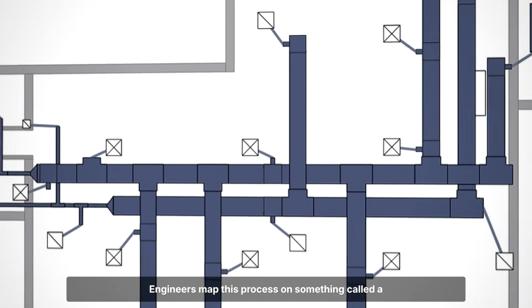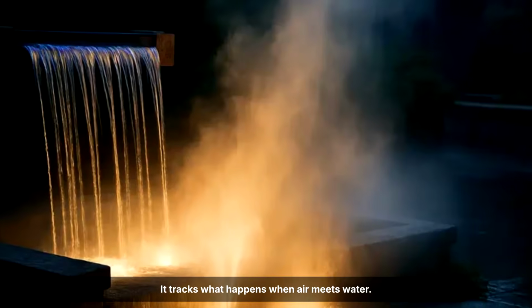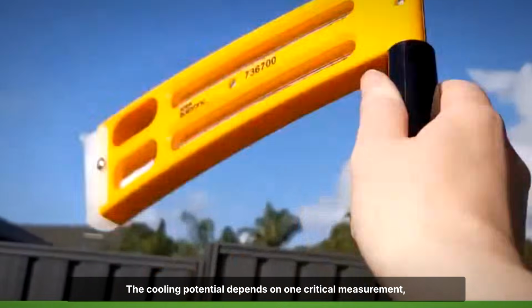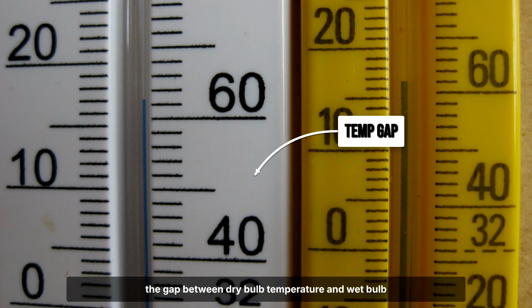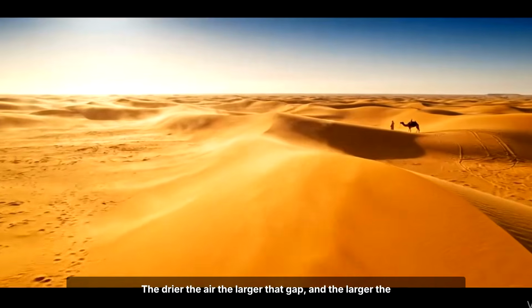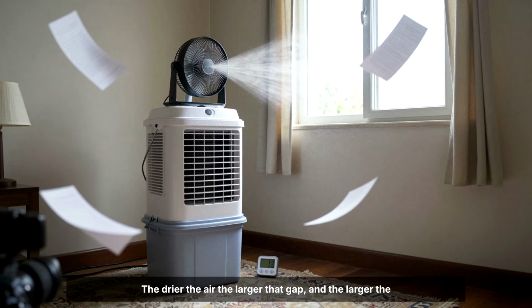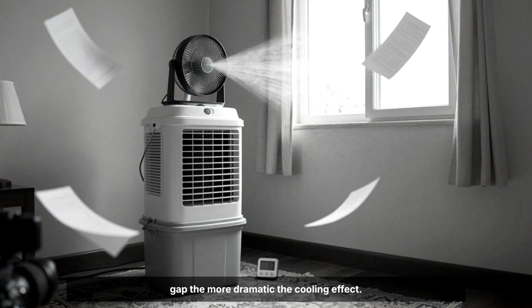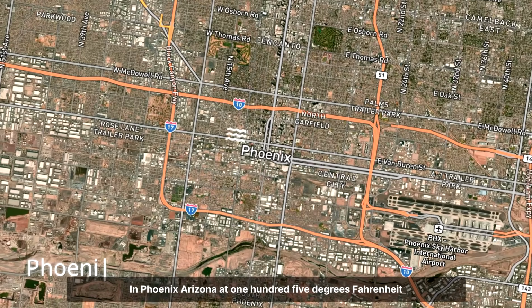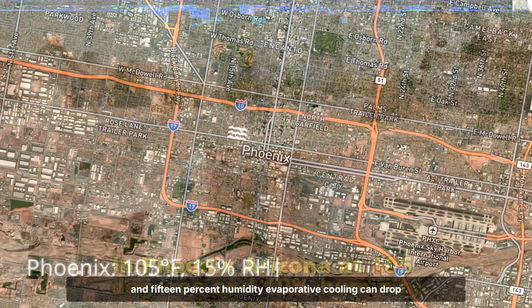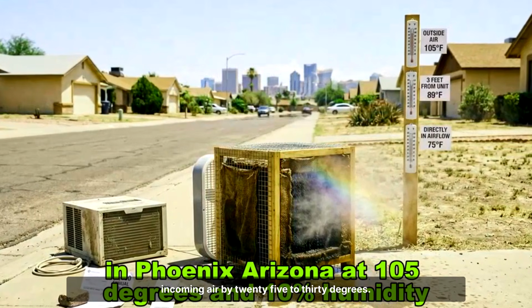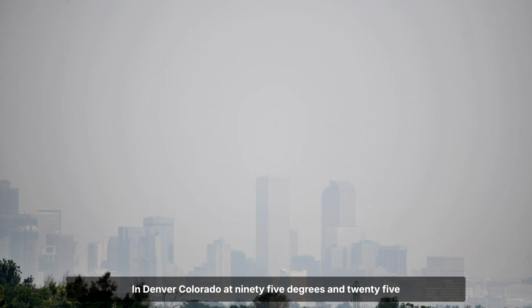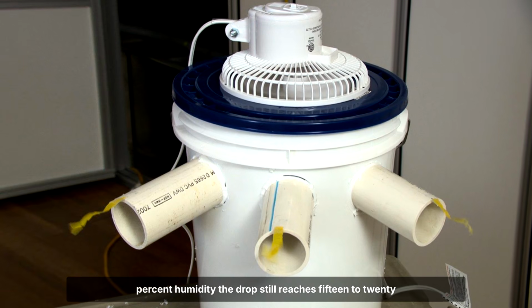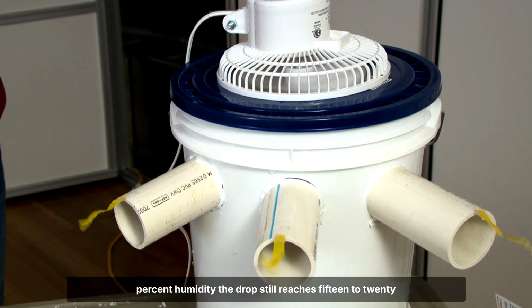Engineers map this process on something called a psychrometric chart. It tracks what happens when air meets water. The cooling potential depends on one critical measurement, the gap between dry bulb temperature and wet bulb temperature. The drier the air, the larger that gap, and the larger the gap, the more dramatic the cooling effect. In Phoenix, Arizona, at 105 degrees Fahrenheit and 15% humidity, evaporative cooling can drop incoming air by 25 to 30 degrees. In Denver, Colorado, at 95 degrees and 25% humidity, the drop still reaches 15 to 20 degrees.